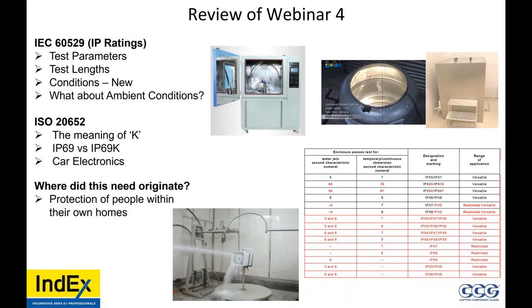So, why? Well, IEC 60529. There are different test parameters and test lengths, during new conditions, but what about ambient conditions? This is a question for later in the presentation. But basically, on the right here, this tank is an IP67 or 68 test tank. On the left is for IP53 or 54. On the bottom here is an IP66 test with direct jets of water.